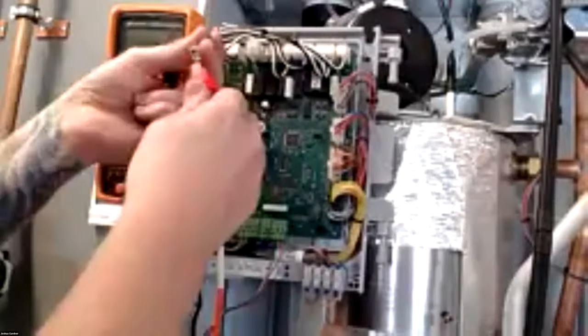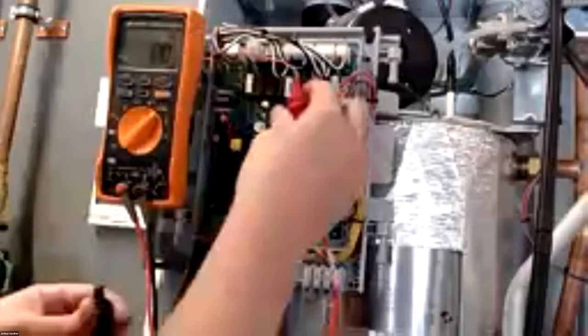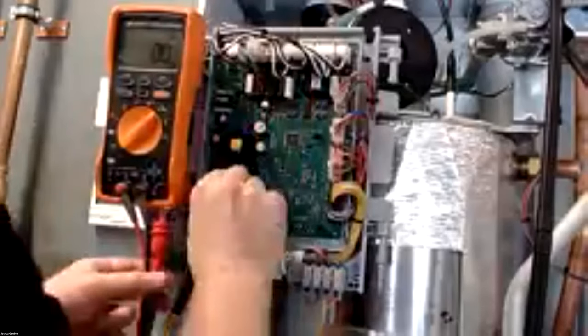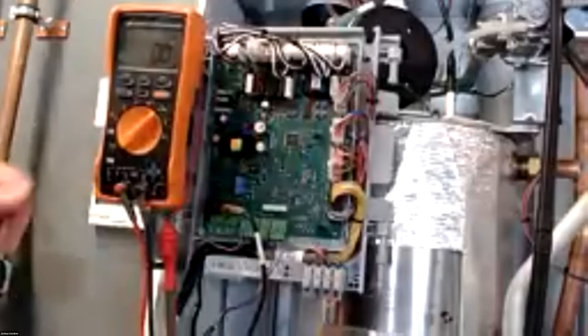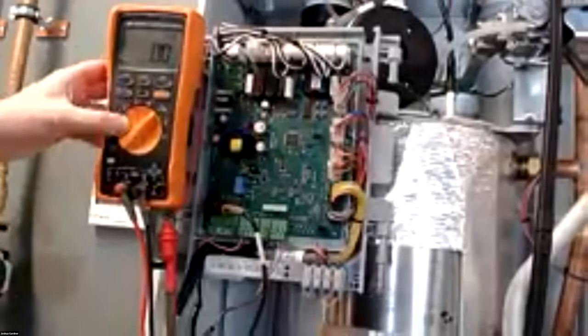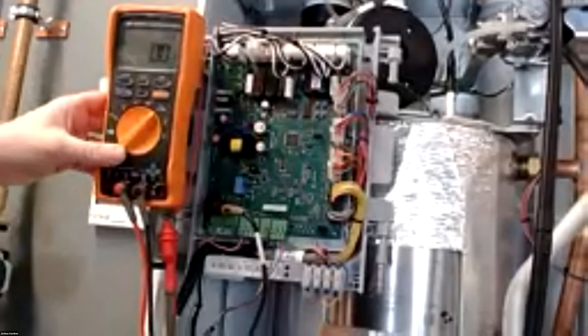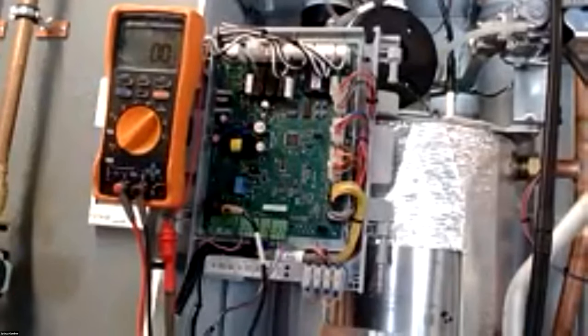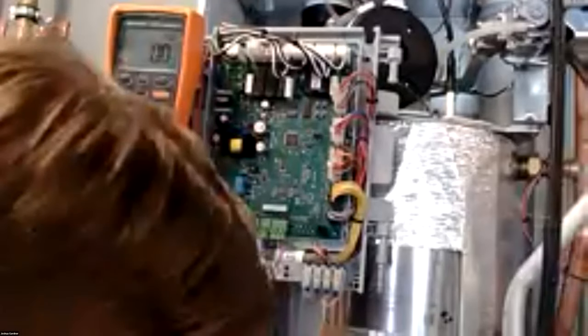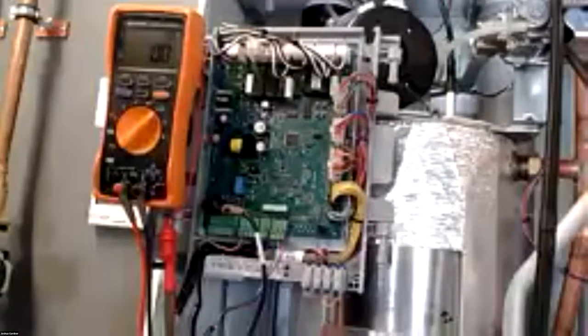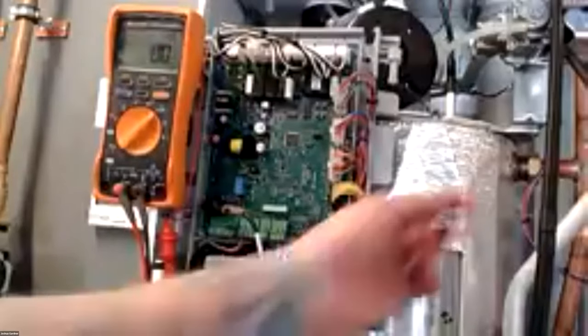Yep. So microamps, somebody asked this, you're just going to have one lead coming from the ignition module. And then you have your other lead down there. Should be a microamp signal. Brand new meter, so still getting used to this one. I like my UEI one better. Let's see, let's fire this thing off. Turn it on first. Somebody asked about the microamp signal, so I'm going to go ahead and set that test up right now.